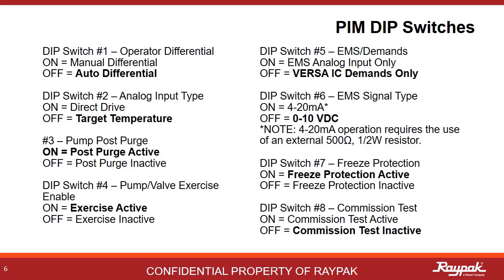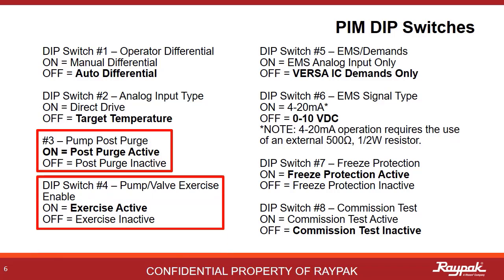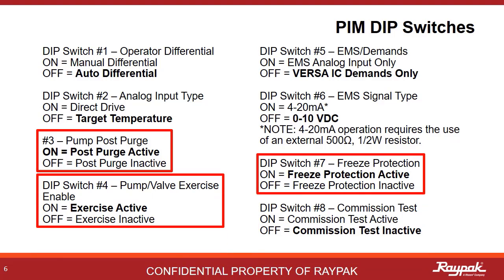A handy thing to remember is that in most cases, without a building management system, the typical setting for the PIM dip switches are number three, four, and seven on, all others off.